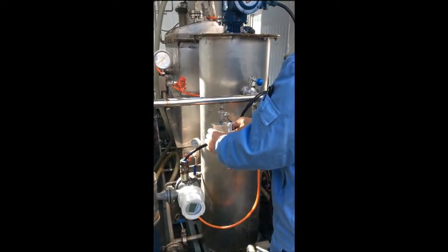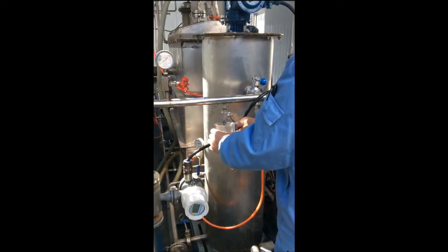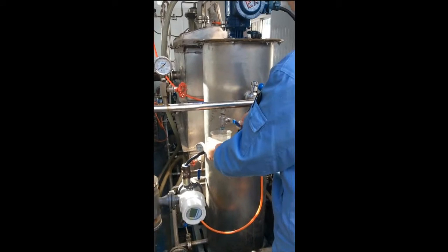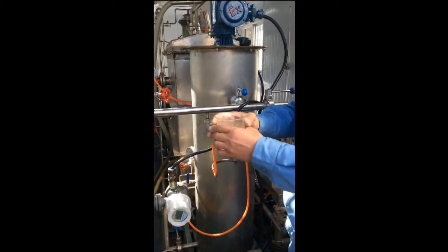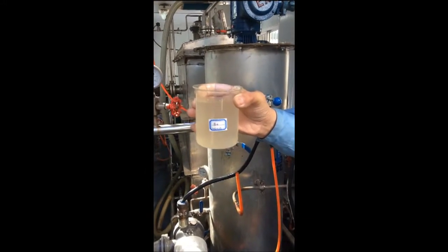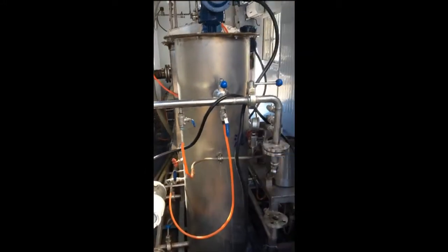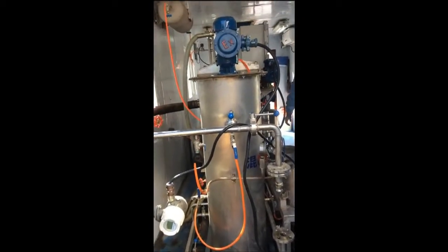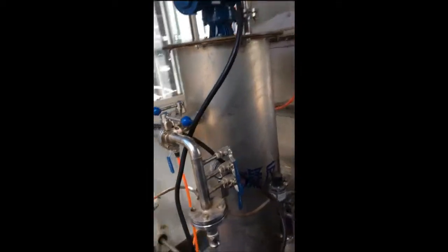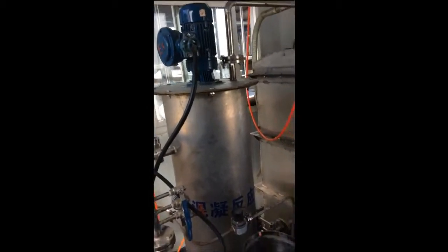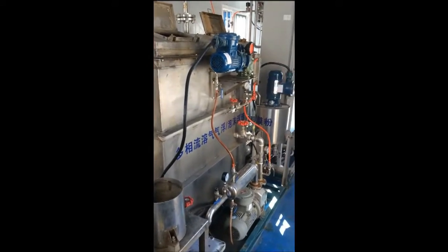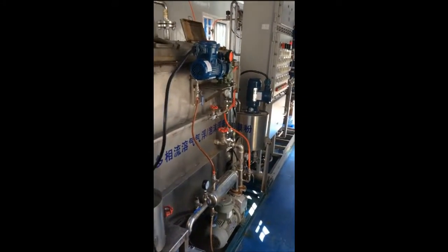This is a sample of the water that is going into the flotation cell. This would be the raw cooling water, and it is about 150 NTU as far as turbidity. This particular plant also has the ability to operate with nitrogen in environments where there is high H2S. In this particular case, we were not using nitrogen. We were using a froth air flotation system.